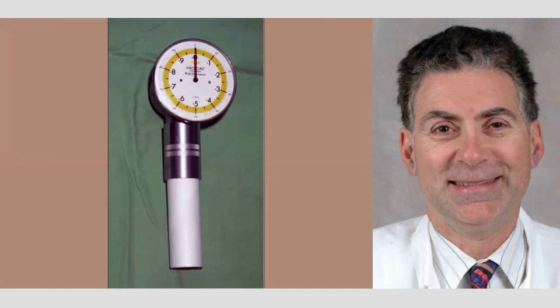We get a non-digital spirometer. And for many reasons, it's better to have a spirometer that is not digital. One of the reasons is that when we measure something that we call air stacking or active lung volume recruitment, we have to get consecutive volumes of air. And with digital devices, they usually don't allow you to do consecutive volumes of air. So we add up those volumes and we get a maximum insufflation capacity, or the air stacking ability of the child. Many digital devices will not allow that. And I will explain that further later on. So I recommend a non-digital spirometer.